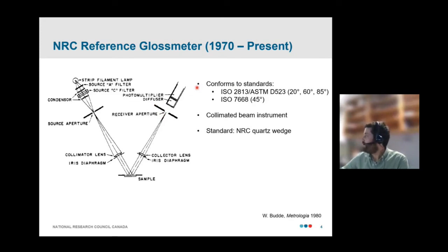A few other notes about our instrument. This instrument's designed to conform to ISO 2813 and ASTM D523, as well as ISO 7668, which includes this additional 45 degree angle of incidence. It's a collimated beam instrument, and as our standard, we use these NRC quartz wedges that Clarence described. And so, in a standard measurement, we would make a recording with our test sample, and then we would swap in our quartz wedge in order to obtain an absolute gloss reading.